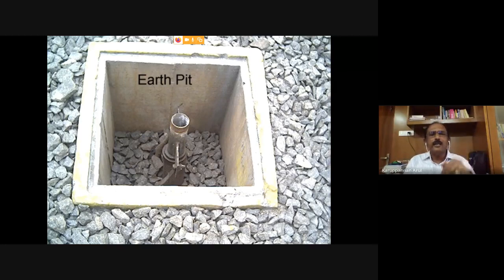So the earthing is done in an earth pit so that the resistance is very low. This earth pit should have a minimum 2 to 3 meter depth of highly conducting GI pipe, and it should be with salt and charcoal inside it. The earth pit should not have any grass or greenery, and it should be covered with granite, and it should be kept wet frequently for better connectivity and lower resistance.